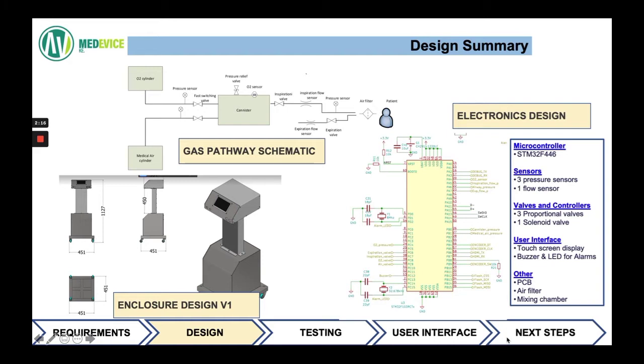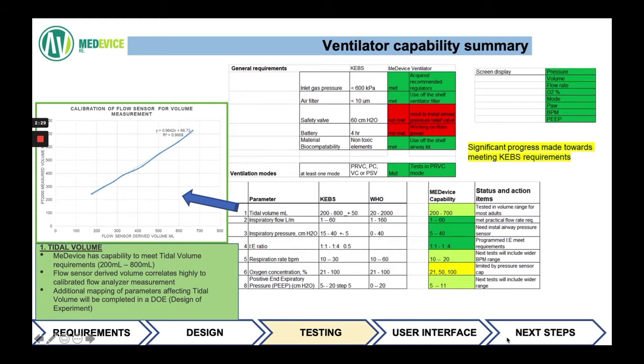Our design takes into account the gas pathway, has an electronics controller, and also has a custom designed enclosure. We have done extensive testing of the capability, and we have made significant progress towards meeting the KEBS requirements. Our tidal volume is between 200 and 800 milliliters. Our inspiratory flow is between 1 and 60 liters per minute. Our inspiratory pressure is between 15 and 40 centimeters of water. Our IE ratio, or inspiratory to expiratory ratio, is from 1 to 1 all the way to 1 to 4.